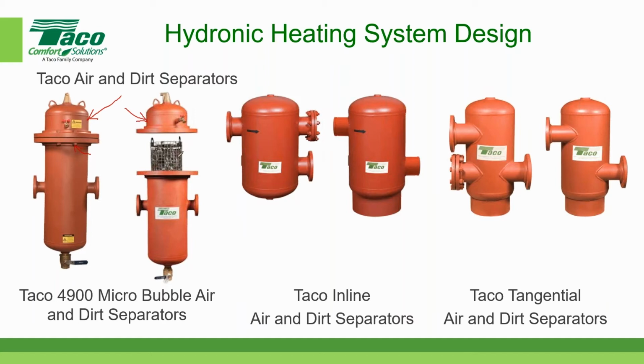And it has a basket, as you can tell from the exploded view here, that is filled with Pall rings. And those Pall rings allow the fluid to change direction thousands, perhaps even millions of times, and allow the air to be extracted from the water. And very, very tiny bubbles. That's why we call them microbubble, because it's the size of just a few microns. So we can get nearly all of the air out using this type of device. The microbubble is probably the most popular that we provide out there. It's the one that does the best job. And as you can see, again, think of the piping system as being fixed. In this case, let's say it's connected to the piping system.